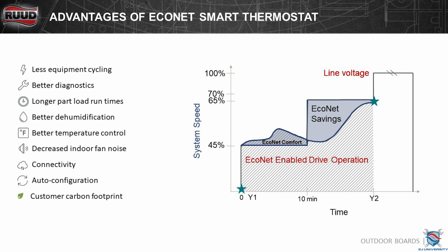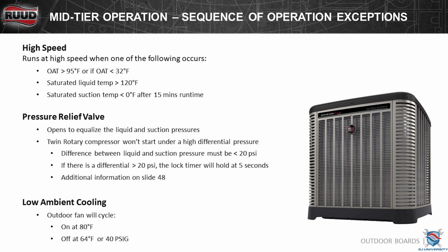Just a little overview graph of the difference in the Econet and the energy savings with the Econet versus running it with a 24 volt thermostat. Few conditions will change that. If your outdoor temperature is over 95 degrees, saturated liquid temperature is greater than 120, or saturated suction temperature is less than 0 degrees Fahrenheit after 15 minutes runtime, then it's going to change how it looks at the staging. It'll jump to a higher stage faster. These will do low ambient cooling as well.